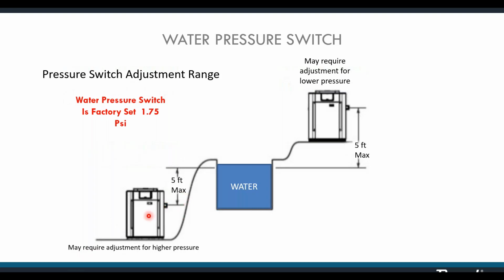So if you're down here below the water surface, remember the water is coming downward through the pipes. Those pipes hold enough water to generate enough pressure just from the gravity to close the pressure switch. So as you begin to install below the water surface, you can adjust that pressure switch to require more pressure. You can do that up to about 5 feet. After that, you've maxed out the pressure switch, and you'd have to go with either a heavier duty pressure switch or a flow switch. If you're up here, on the other hand, a pressure switch isn't going to do you any good, because the water traveling downward from the heater back down to the pool is also being acted upon by gravity. It's being pulled downward.